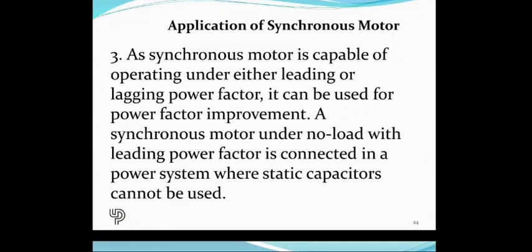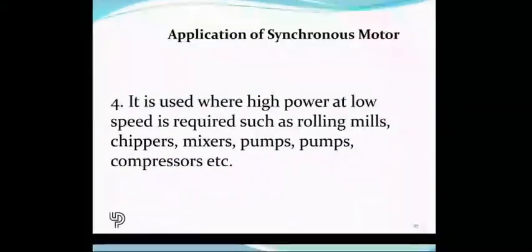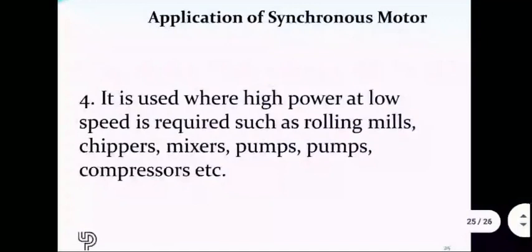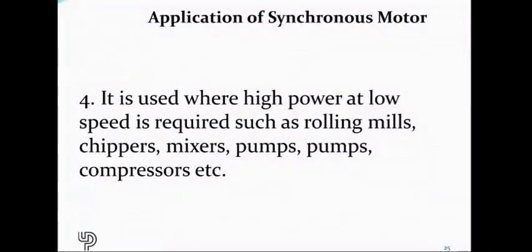Applications. One application is, because it can work with both leading and lagging power factors, it can be used for improving power factors in real life. That's one application for sure. And wherever you need constant speed operation in industry, this could be a very good fit. Rolling mills, chippers, mixers, pumps, compressors, etc., are where synchronous motors are frequently seen. Okay, so this is almost done.